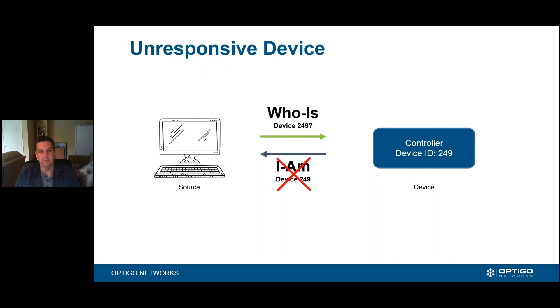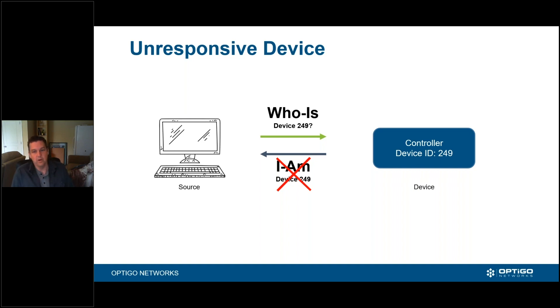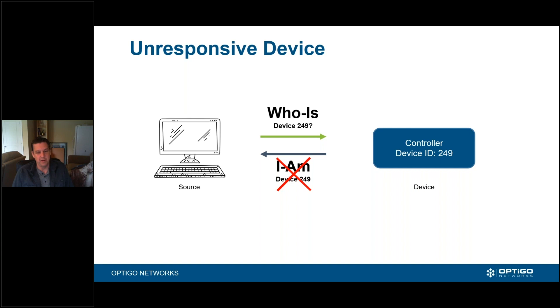However, when we have an issue, it now becomes an unresponsive device. There's a difference between unresponsive and offline, which is why inside Visual BACnet we call it an unresponsive device. This means that we asked the question — say, who is device 249 — and we did not receive a response. There are a lot of reasons why device 249 is not responding.